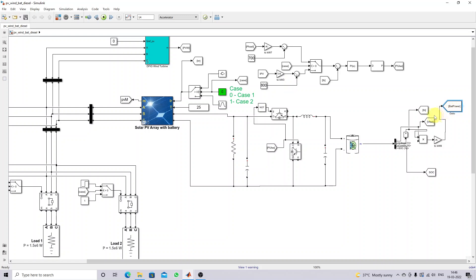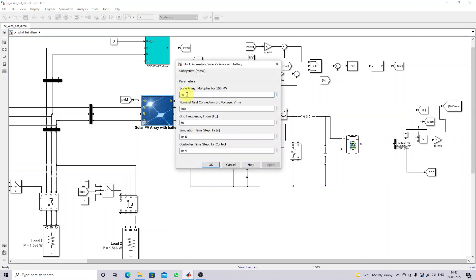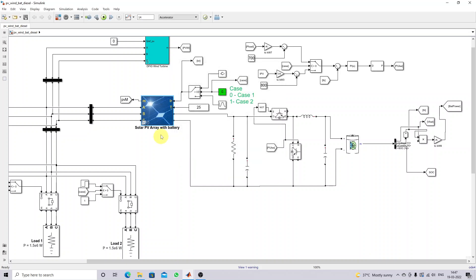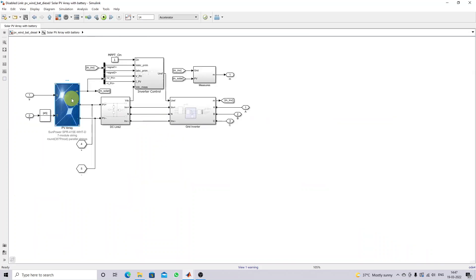Here we are measuring the battery power, battery current, and battery voltage — this is the state of charge of the battery. We are also measuring the power of the PV panel. The power ratings are mentioned in terms of 100 kilowatt. If we put 20, that's 20 × 100 = 2000 kilowatt, which is two megawatt total. The grid line voltage is 400 V, grid frequency is 50 Hz, and nominal power is two megawatt.